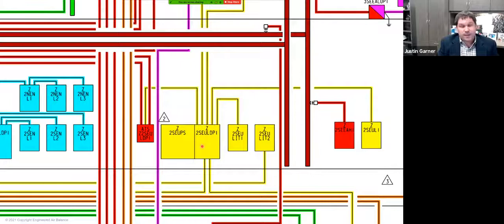This particular model actually had a transformer built in that stepped down to 208. So these are 208/120 panels that are being fed out of this system. And this fed the entire IT infrastructure as well as all the controls in the facility. So it was a really neat setup. We didn't have a lot of the issues with cycling of control panels and things like that. It can cause some other issues. Obviously, the BAS has to know when power is cycling, so it doesn't see equipment that may not be on UPS go down. But that's a conversation for another day. Just recognize, though, that you need to identify whether the systems are uninterruptible or not.